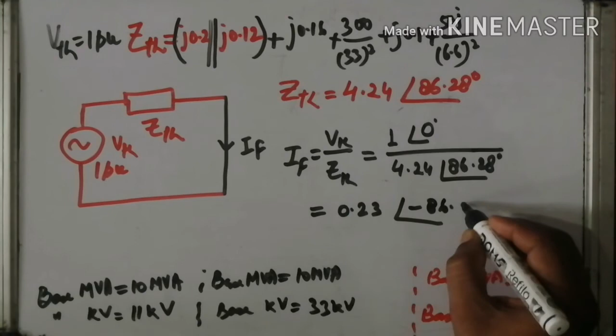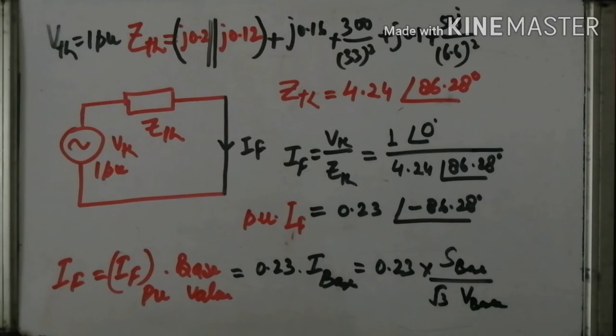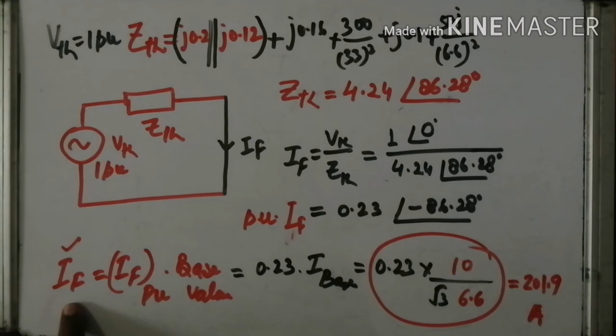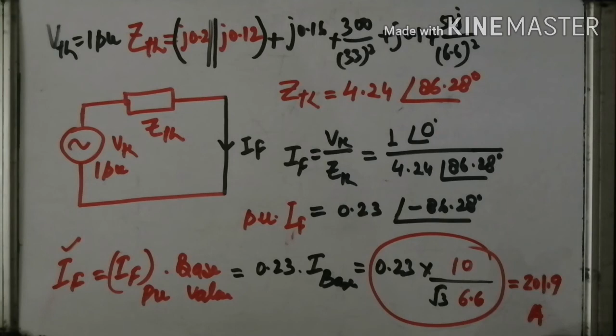But listen to me very carefully. This is the value of current, but in per unit. So for the calculation of the actual fault current, it is necessary to multiply the per unit fault current with the base value. The fault current is 0.23 into I base, and I base is given by S base divided by root 3 into V base, right? The value of S base is 10, and V base is 6.6. After the calculation, the actual value of the fault current is 201.9 ampere. The actual value of fault current in the given circuit is 201.9 ampere.